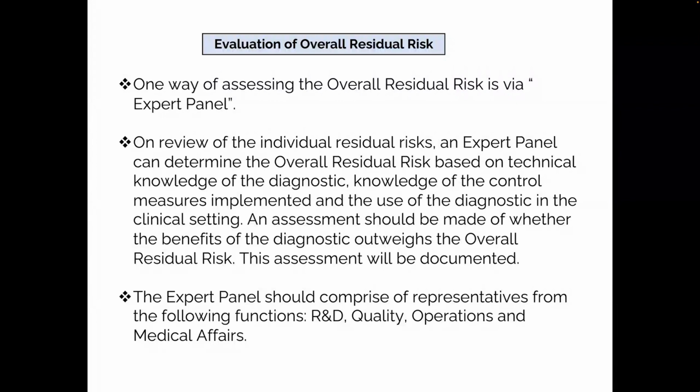Usually they include R&D, quality, operations, and medical affairs, in order to get that combined step back from the risk assessment and say, based on all of this knowledge, I believe the overall risk of the device is acceptable, or it's in the middle zone.